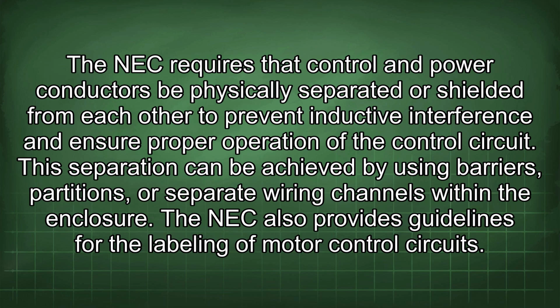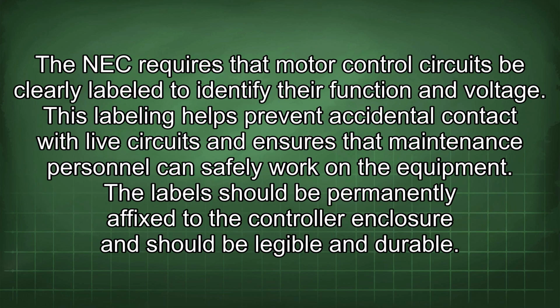The NEC also provides guidelines for the labeling of motor control circuits. The NEC requires that motor control circuits be clearly labeled to identify function and voltage. This labeling helps prevent accidental contact with live circuits and ensures that maintenance personnel can safely work on the equipment. The label should be permanently affixed to the controller enclosure and should be legible and durable.